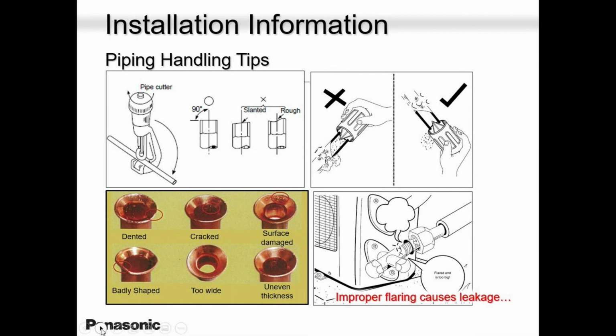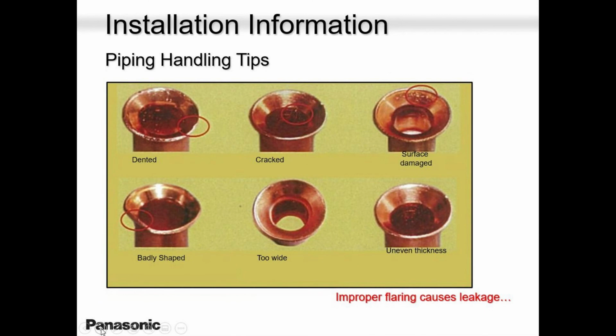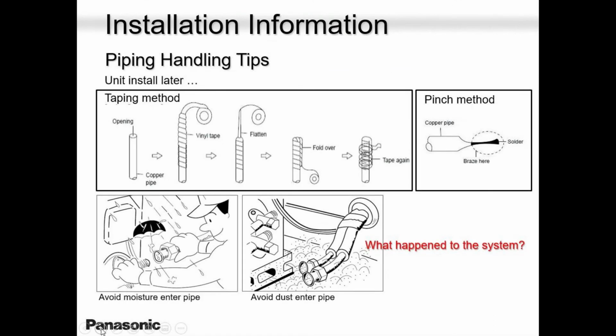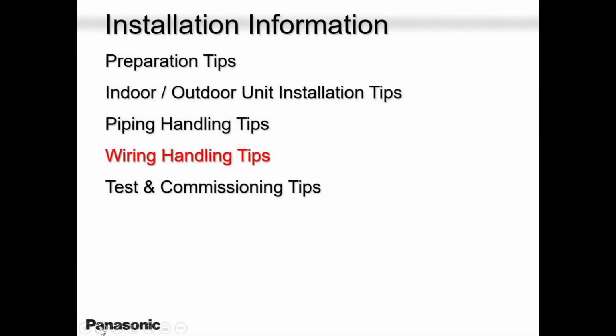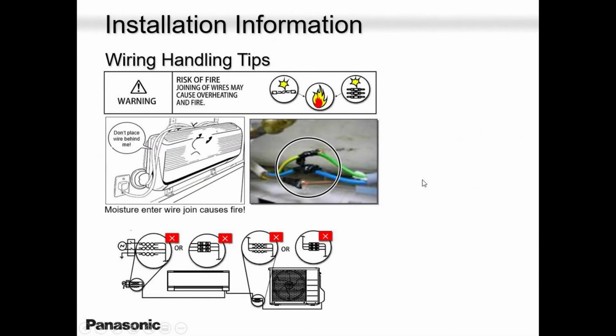These are simple things in installation. They say 99.9% of problems are caused by the installers. So I'm not blaming you guys. I'm not blaming anyone. But always take extra time. Talk to the homeowner while the unit is in test. Talk to the homeowner about how to use it. If the homeowner gets to know what to use and what not to use, they are not going to call you. But if you get callbacks, that's because the homeowner has no time to read the user manual, and we as installers did not have time to talk to them while the unit was getting tested. So it's important that you talk with the homeowner, give them some tips on how to use it, how not to run it like crazy, unnecessarily. Show them how to save some energy.